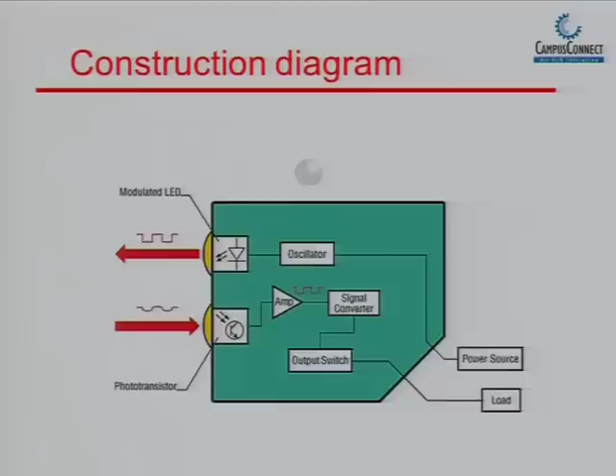In photoelectric sensors it is never a single beam, because if there is a single beam, there is a possibility of noise or dust interfering with the signal. So there are multiple pulses and they are going at very high frequency. If you look, it looks like a single beam, but they are all pulses. So even if a single pulse gets obstructed, there are multiple pulses following it, which can still give you feedback. Let me extend the question or give you a hint.